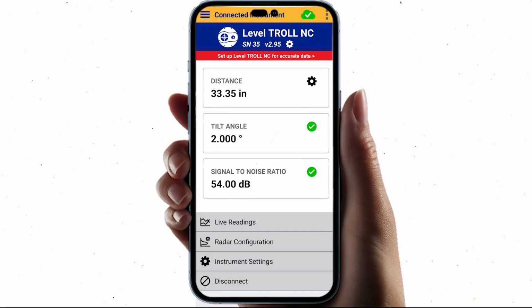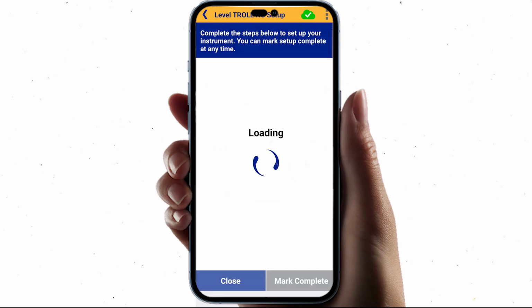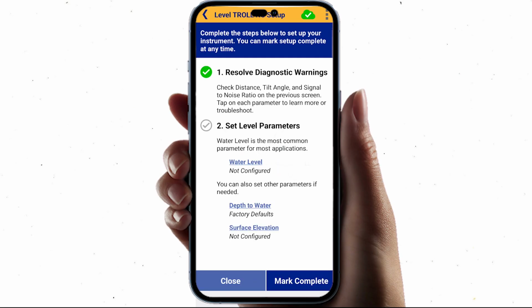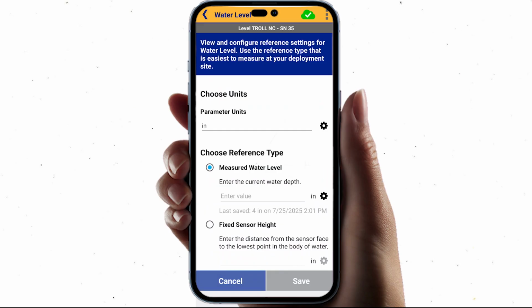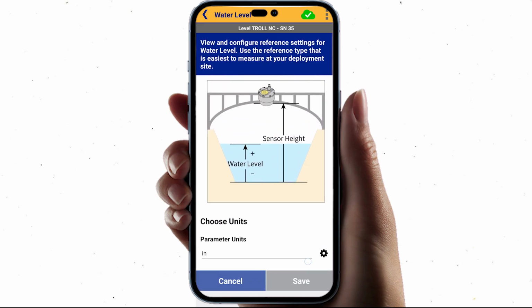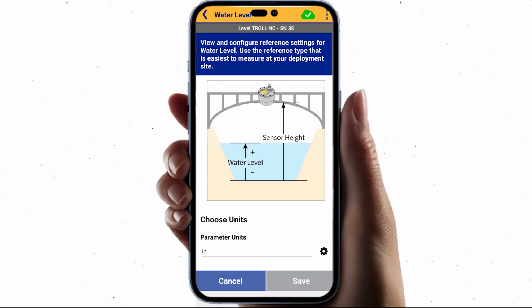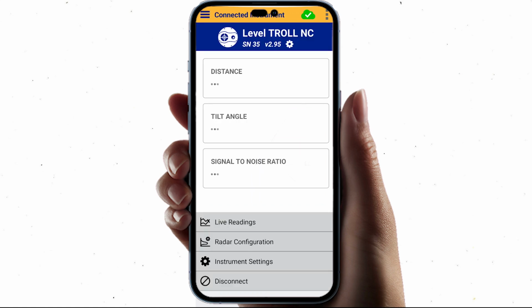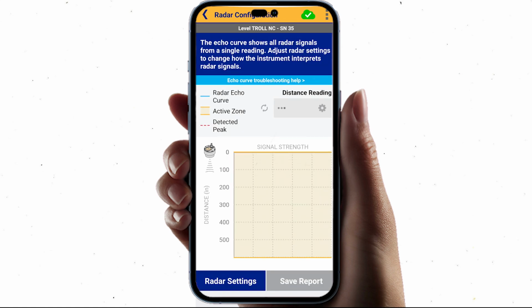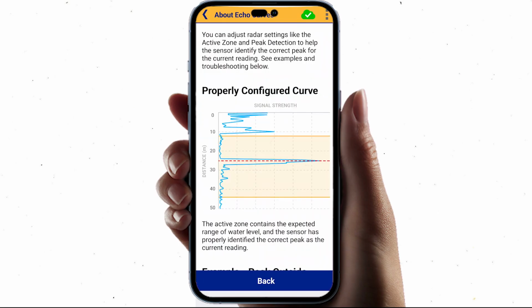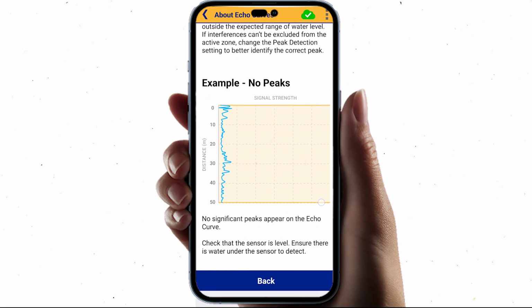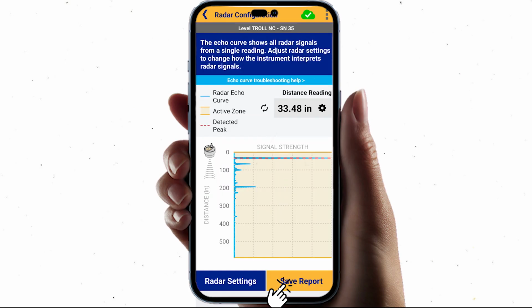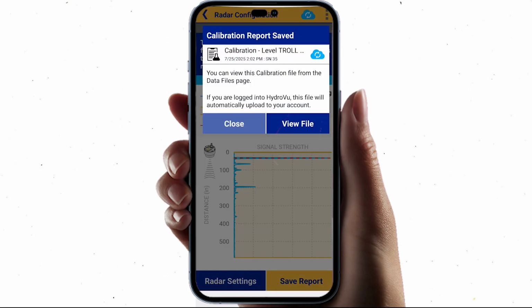When the values are all green and the distance measurement looks correct for your deployment site, you can tap the banner to finish setting up your instrument. Here, you can add the reference measurements you took from your deployment site. You can always update these measurements later from the VuSitu Instrument Settings menu. On the radar configuration page, you can view the echo curve for the instrument and troubleshoot any issues with the radar readings. There's troubleshooting help right there in the app, or you can view the manual on In-Situ's website. Tap Save Report to save a report of the configuration for your records.